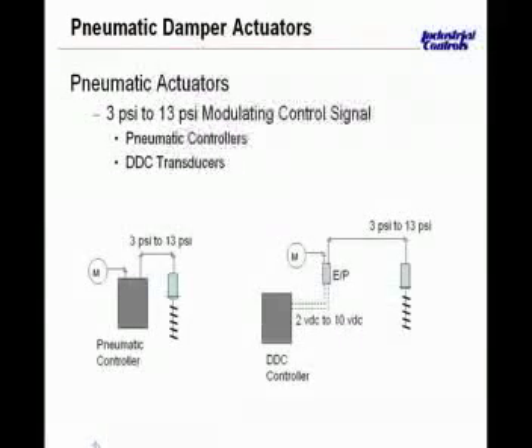Okay, let's move on then to damper actuators and how they may be interfaced to a direct digital control system or any kind of electronic control system. This picture on the left-hand side has main air pressure coming into the controller, as you learned in the last session, and then this pneumatic controller is outputting out of the branch line a variable air signal. In this particular case, it's 3 to 13 pounds psi, and that may be dependent on different manufacturers. So this then changes, modulating to full 3 to 13 pounds. At 3 pounds, there's no air pressure on here. This rod would be fully inside the actuator, and as it's modulated from 3 pounds up to 13 pounds, the air pressure would build up and then extend the stem out of the actuator.